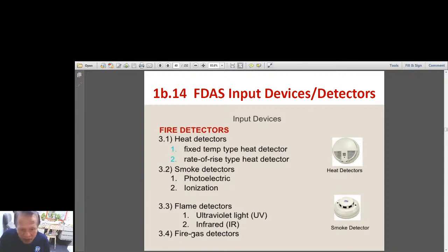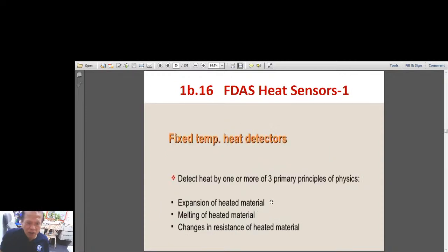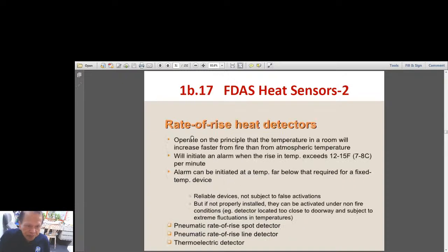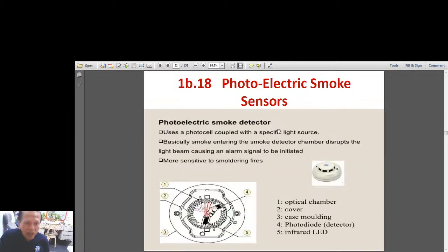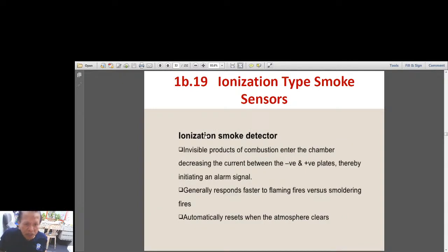Okay, the fire gas detector is the same. You already have a gas, so you must have something like a toxic gas detector. Okay, so here is just the description for the heat detector: fixed temperature type and rate of rise heat detector. Okay, and now we go to the photoelectric detector. So the smoke detector, photoelectric in nature. This is the most common detector. And the ionization smoke detector has a little difference in the operating characteristics. The ionization is a lot more expensive, but it is sometimes best suited for some addressable applications.